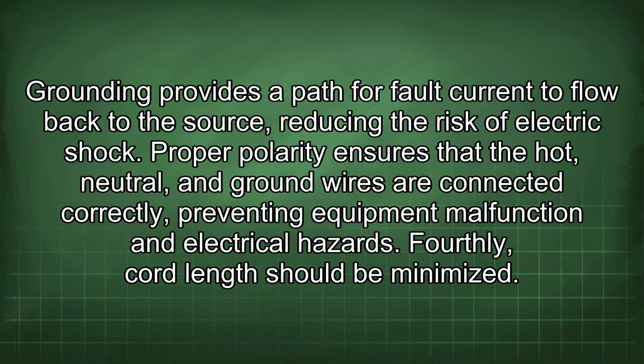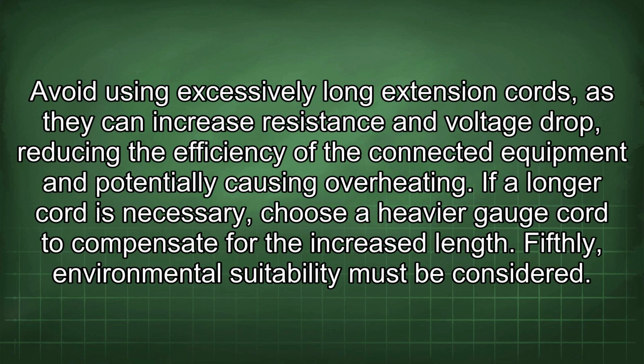Fourthly, cord length should be minimized. Avoid using excessively long extension cords, as they can increase resistance and voltage drop, reducing the efficiency of the connected equipment and potentially causing overheating. If a longer cord is necessary, choose a heavier gauge cord to compensate for the increased length.